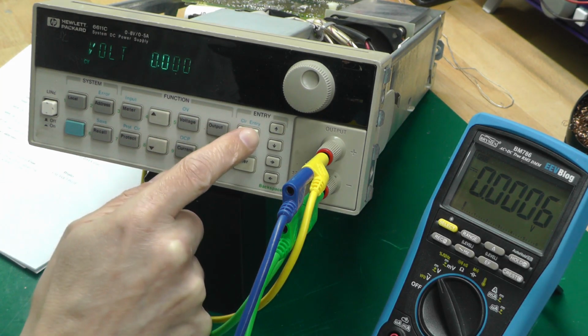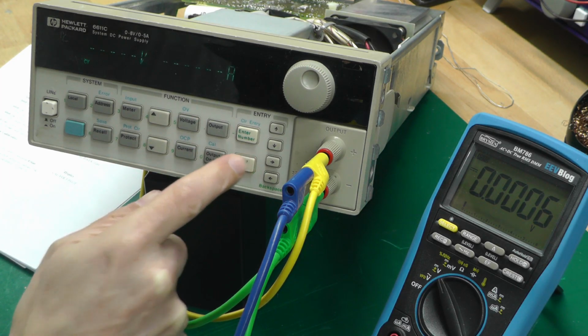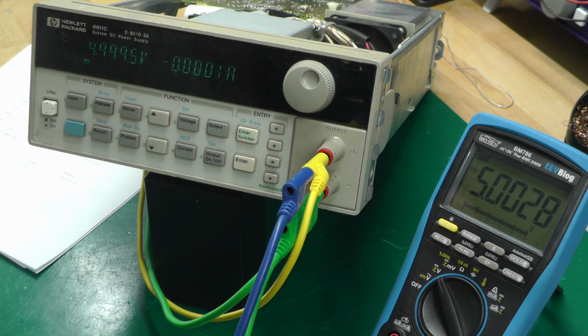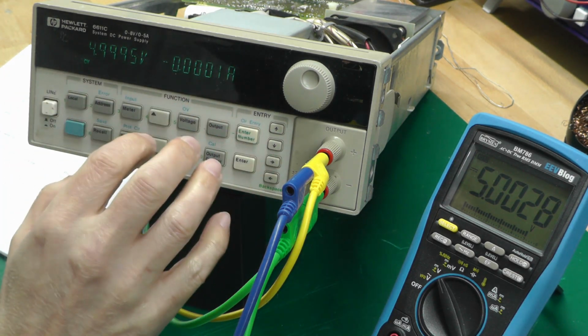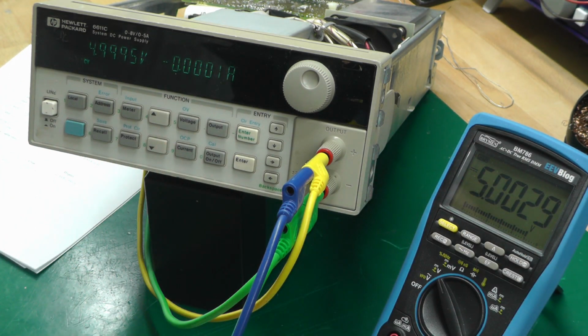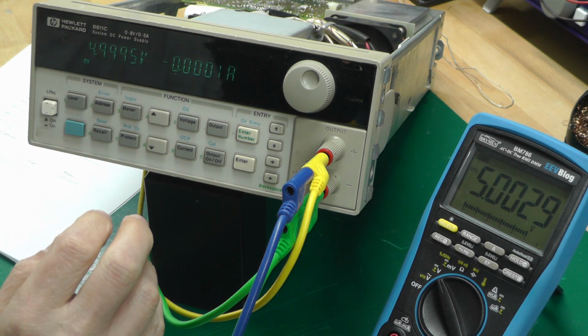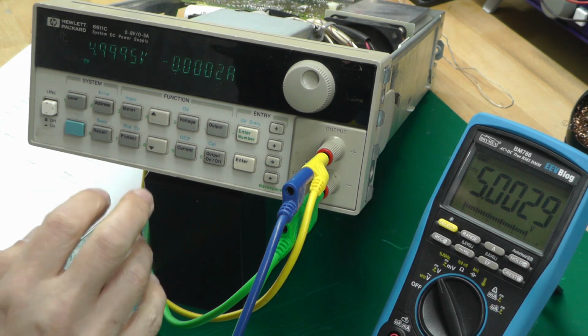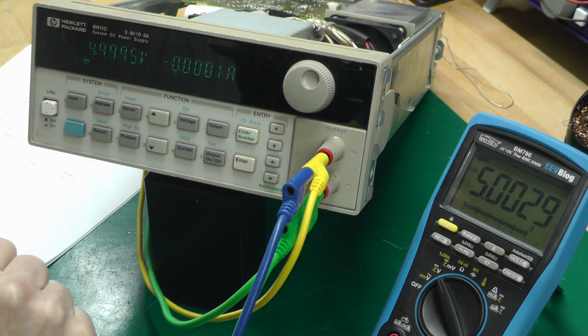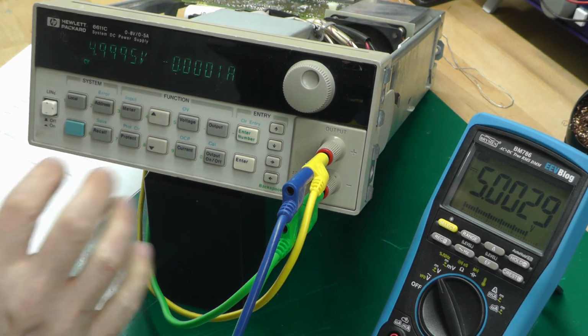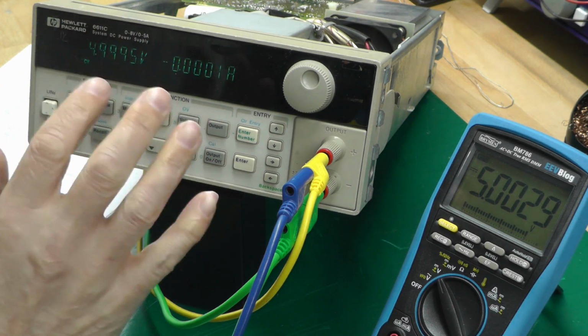So voltage, enter number, 5 volts. Look at that. Perfect. It's not bad. 5.0028 for 4.9995 on the display there. I could probably tweak the entered value in to bring this closer, but I am just using my BM786, so who knows how accurate that is. For calibration I should really be using something like my Keysight 34461A to get the level of accuracy needed for a proper recalibration, but I can do that at a later date once I get the cover on the unit, once I know it's recalibrated.